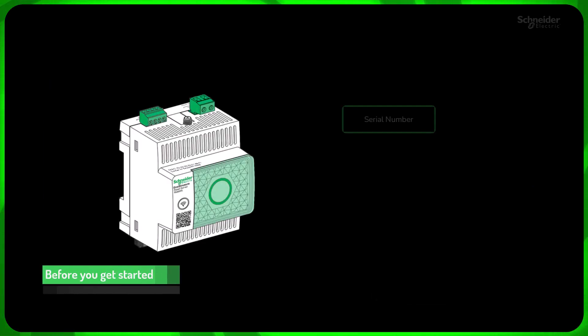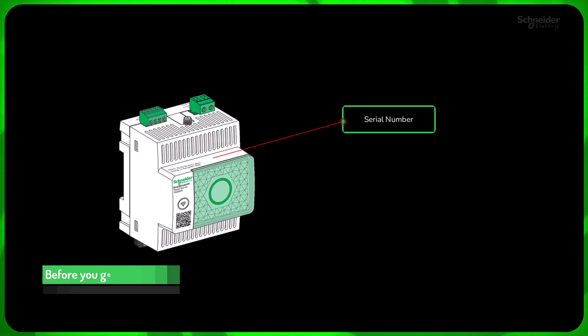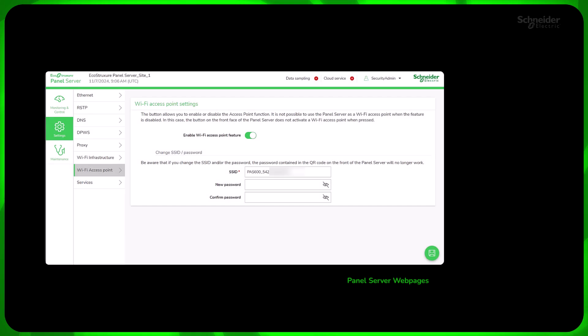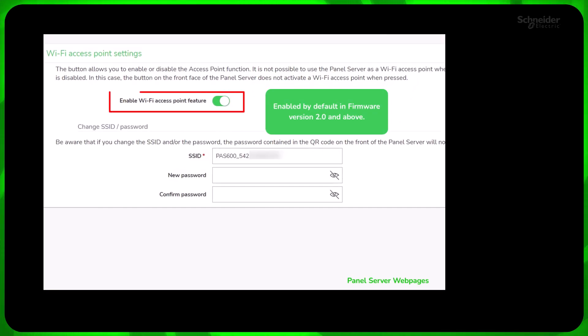Before getting started, please verify the serial number of your panel server. If it begins with the sequence 542.5101 or higher, it has firmware version 2.0 or above. The access point feature is enabled by default. However, if you previously disabled it, please re-enable this feature on the web page.